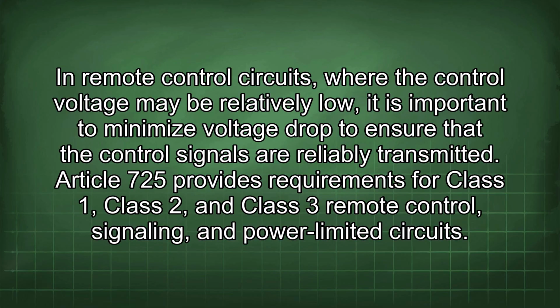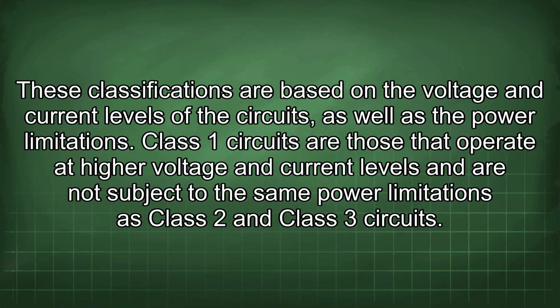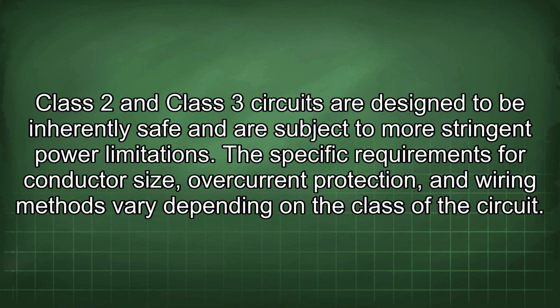Article 725 provides requirements for Class 1, Class 2, and Class 3 remote control, signaling, and power-limited circuits. These classifications are based on the voltage and current levels of the circuits, as well as the power limitations. Class 1 circuits are those that operate at higher voltage and current levels and are not subject to the same power limitations as Class 2 and Class 3 circuits. Class 2 and Class 3 circuits are designed to be inherently safe and are subject to more stringent power limitations. The specific requirements for conductor size, overcurrent protection, and wiring methods vary depending on the class of the circuit.